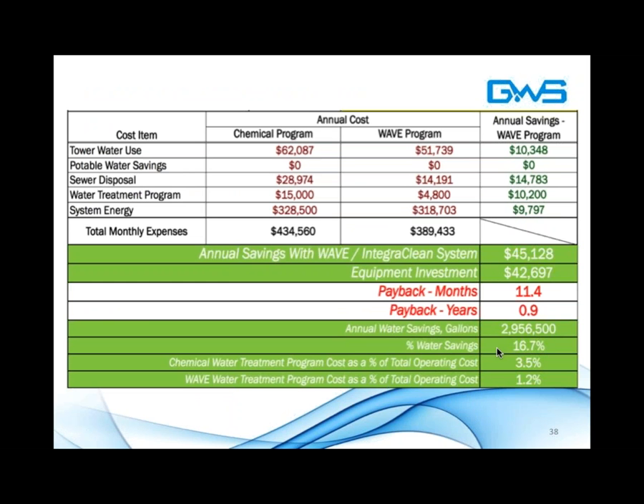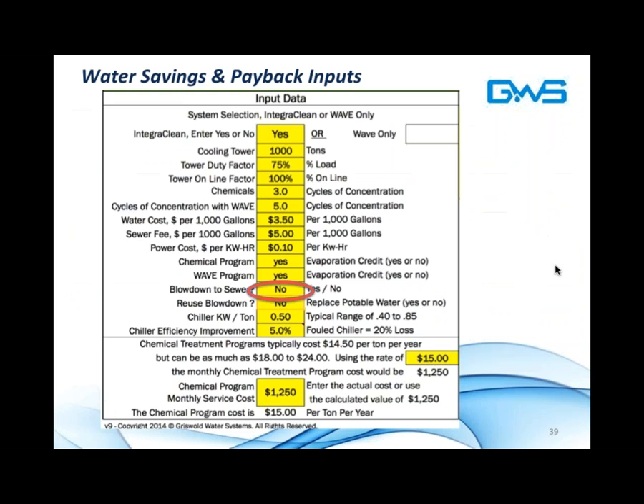In this case, you can see that the chemical water treatment program cost was about 3.5%, so a little higher than my earlier figures. But wave water treatment cost is more like 1.2%. That shouldn't really concern the owner-operator. What should concern the owner-operator is the operating cost, because what we're talking about are annual savings of $45,000. That leads to a less than 1 year payback, of course, but those annual savings are certainly significant when factored over the life of the equipment.